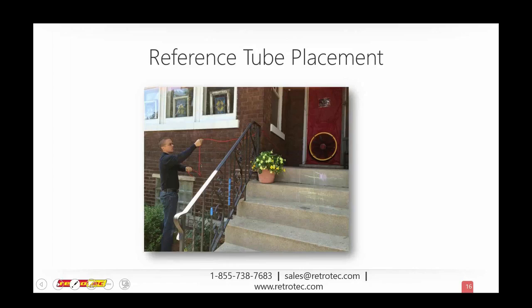Okay. Here's another issue that we have quite a bit. We're going to talk a little bit about our reference tube placement, and sometimes with the duct tester, it can actually be the input as well. But we have a problem sometimes with reference tube placement, and simply put, this is a pressure gauge. A manometer is a differential pressure gauge. So it's always telling us the difference between 2 points. It's not telling us absolute pressure.